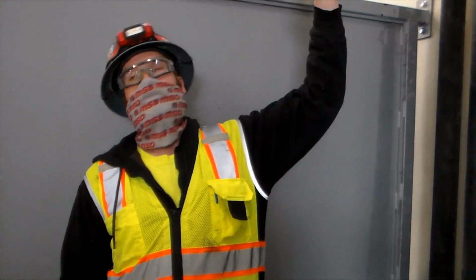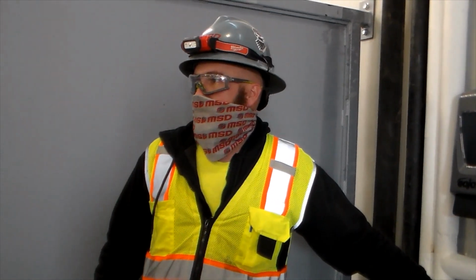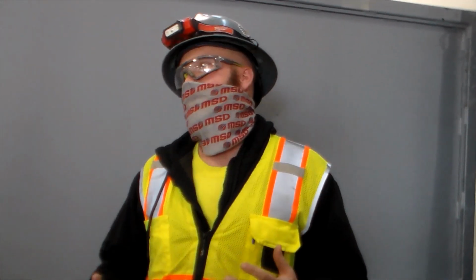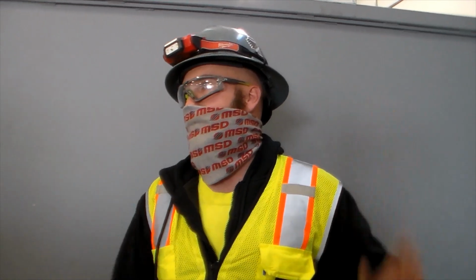We have multiple instant hot water heaters throughout the building. You'll hear that contactor click in. You'll get hot water after a couple seconds, and you hear it shut off. The maintenance points on these would be, check the wear on your contactor. And these have 3 to 4 elements in them, depending on the size. If you ever have to change the elements and drain the water, make sure you flow through your hot side before you turn the elements back on, or they will burn up.